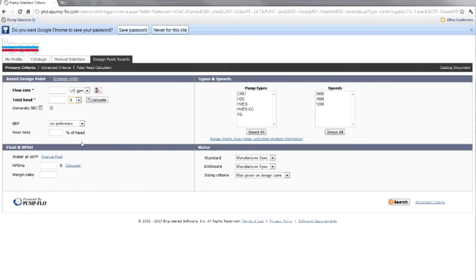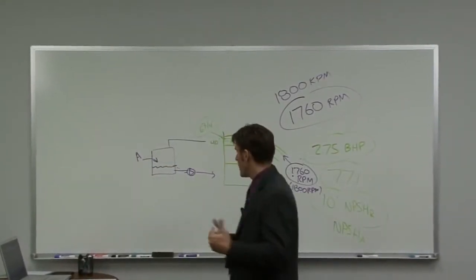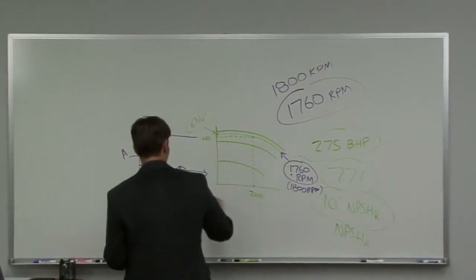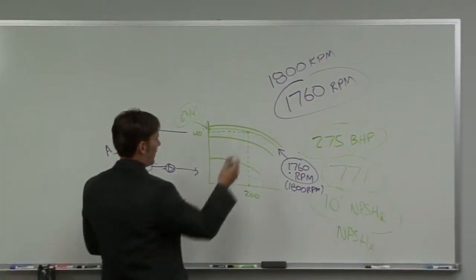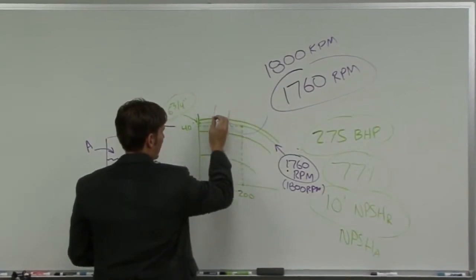Let's select a pump for an application for 750 gallons per minute at 55 feet of head. Now, before we do anything else, there are some other conditions that we need to look at. We can tell it whether or not we want to be left of best efficiency point or right of best efficiency point. Now, when we talk about left or right of best efficiency point, again, we're looking at these efficiency curves that drop in like this.